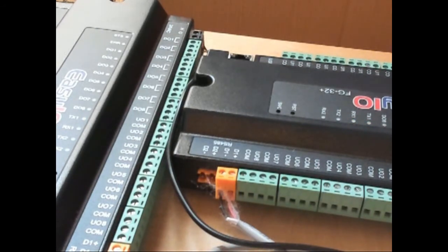Now, see the two lights flashing? You can certainly see it on the right-hand controller, and you may see it on the left one, but they are both flashing, and that means we have a good electrical connection between the two. This is very important when you're adding any BACnet devices to make sure the electrical connection is correct. If these two lights are not flashing, the FG client will not discover the MSTP server devices. So please check the baud rates, make sure the connections are correct, and get those two lights flashing beforehand.